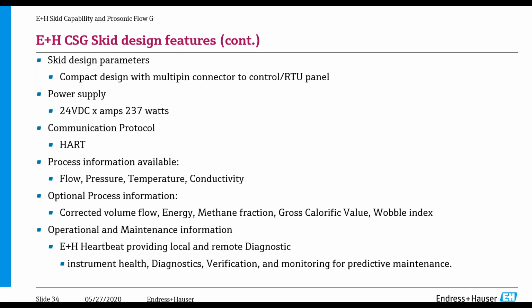Power supply: it's a 24-volt DC power supply to the system. It's using 237 watts. In some remote applications, power consumption is obviously a concern, and we've kept the power consumption as low as we possibly could on the skid itself. Communication protocol: on the standard Endress+Hauser offering, it's HART, but as I mentioned earlier, it's also available in Ethernet IP, and there are some added advantages to using Ethernet IP in terms of integration into the Rockwell system as well. Process information available on the standard offering is flow, pressure, temperature, and conductivity.